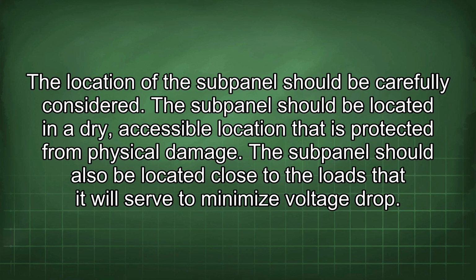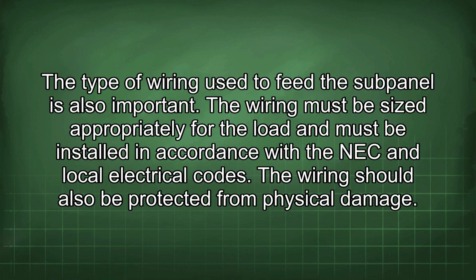The subpanel should be located in a dry, accessible location that is protected from physical damage. The subpanel should also be located close to the loads that it will serve to minimize voltage drop. The type of wiring used to feed the subpanel is also important. The wiring must be sized appropriately for the load and must be installed in accordance with the NEC and local electrical codes. The wiring should also be protected from physical damage.